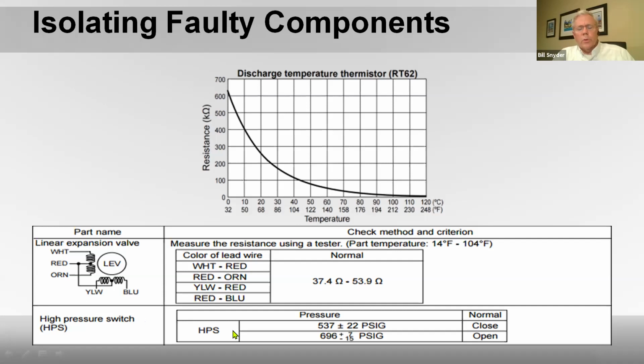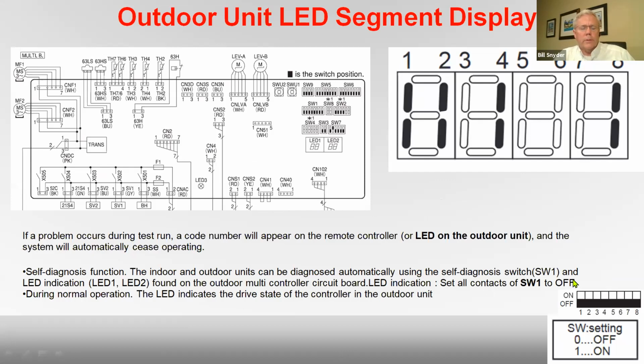And then the high pressure switch. Remember we talked about leak testing and we said check to 600 pounds. Well, you'll see that this high pressure switch opens at 696 pounds. So we've got no problems. You've got almost another 100 pounds in there before that thing will open when you're checking for leaks.